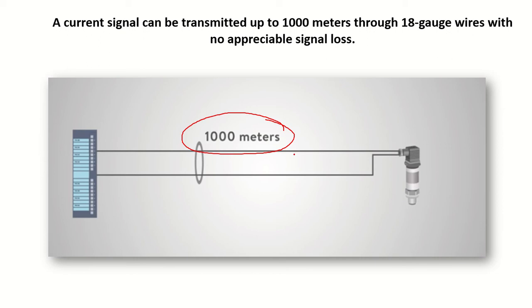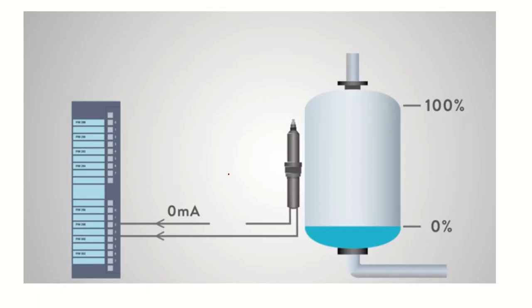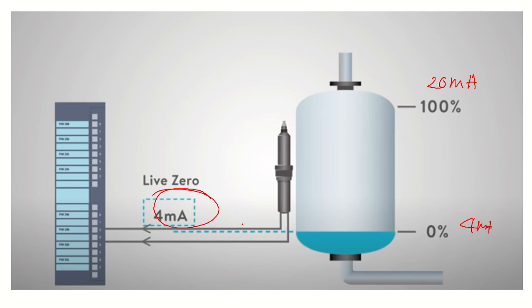Data can be transmitted through an 18-gauge wire without any appreciable loss. Another important advantage of current loops is the live zero feature. The lower range limit is 4 milliampere and the upper range is 20 milliampere. If the output gives 0 milliampere, that means there is some disconnection in the wire. Since the minimum value should be 4 milliampere, getting 0 milliampere indicates a disconnection — this feature is called the live zero feature.